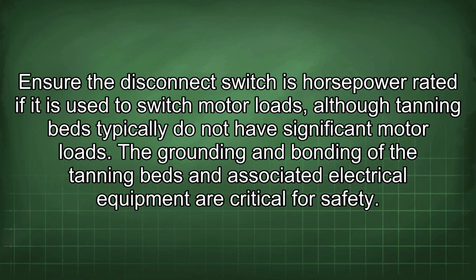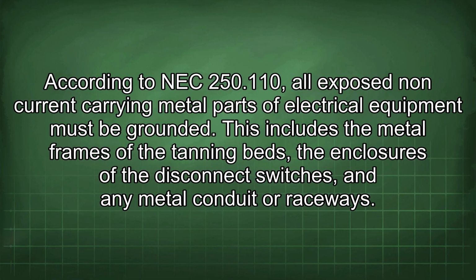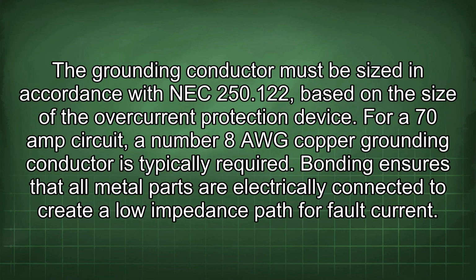The grounding and bonding of the tanning beds and associated electrical equipment are critical for safety. According to NEC 250.110, all exposed non-current carrying metal parts of electrical equipment must be grounded. This includes the metal frames of the tanning beds, the enclosures of the disconnect switches, and any metal conduit or raceways. The grounding conductor must be sized in accordance with NEC 250.122, based on the size of the overcurrent protection device. For a 70 amp circuit, a number 8 AWG copper grounding conductor is typically required.